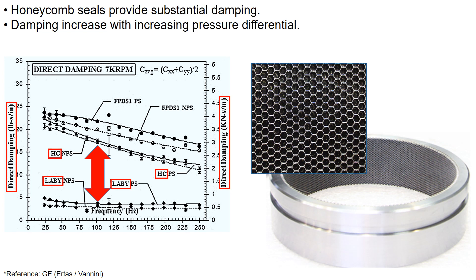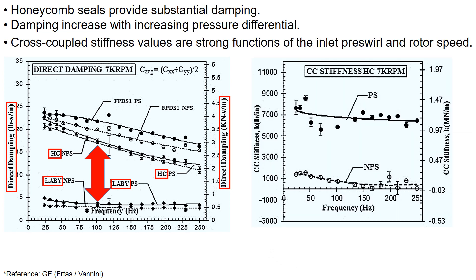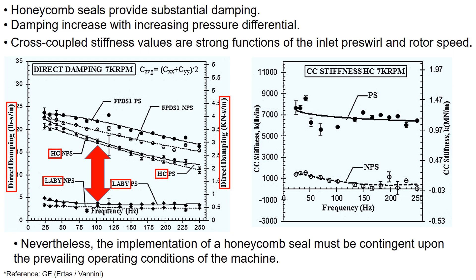Honeycomb seals provide higher damping compared to labyrinth seals, with damping increasing as the pressure differential rises. The cross-coupled stiffness values are highly influenced by the inlet pre-swirl and rotor speeds. Therefore, the implementation of the honeycomb seal should consider the prevailing operating conditions of the machine.